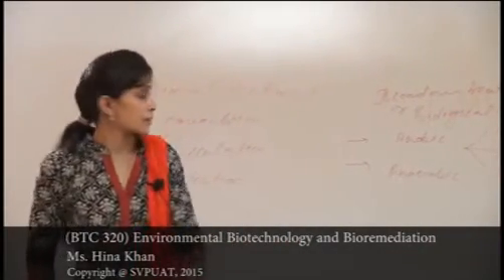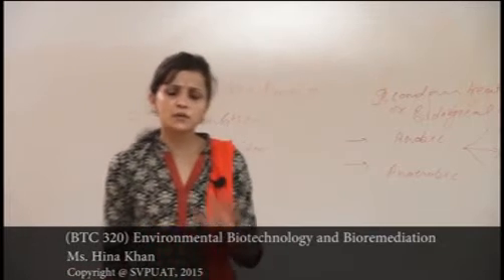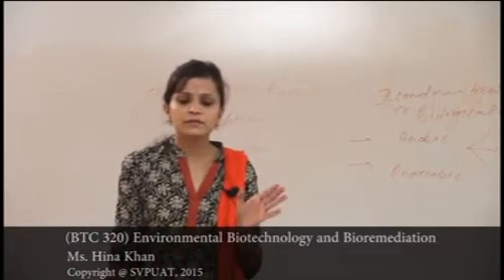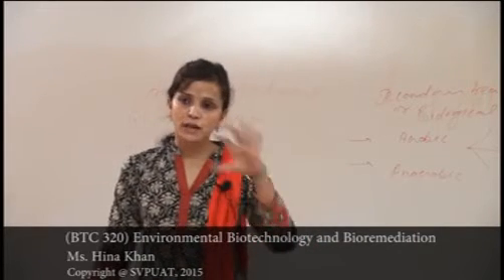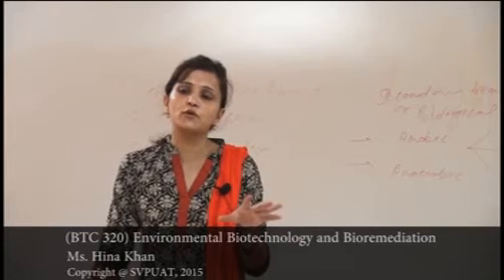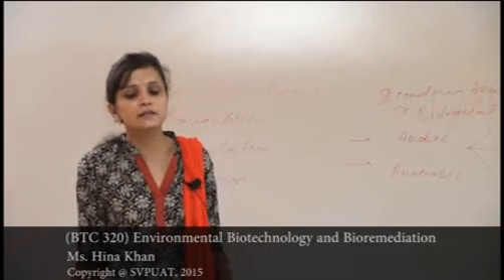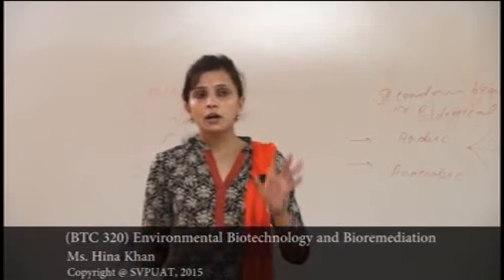The activated sludge process is the most versatile biological oxidation process for wastewater treatment. Sewage from the sedimentation tank enters aeration tanks where oxygen is present for aerobic action by microorganisms. About 20 to 30 percent of active sludge is mixed, aerated, and kept in the tank for about four to eight hours. Microorganisms oxidize the organic matter in the presence of abundant oxygen, and the mixture is then allowed to settle at the bottom of a secondary tank.